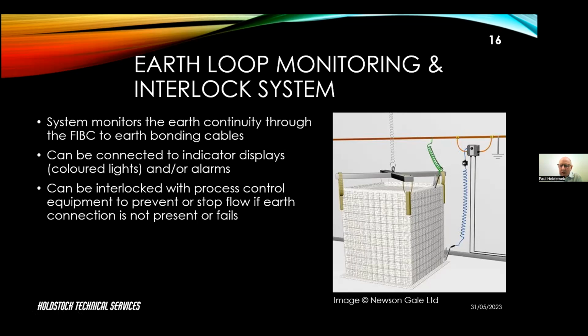And it gives an indication that it could be a display of lights, so a red light, green light, or it may be an alarm that will sound if the resistance goes above 10 to the 8 ohm. There's also the opportunity to connect the monitoring system to an interlock, which will be linked with the process control equipment, which will stop the flow of material into the bag or out of the bag if the earth connection is not present, or if it fails during filling or emptying. So that's a very useful system, which will eliminate a lot of the possibility of human error when handling type C.